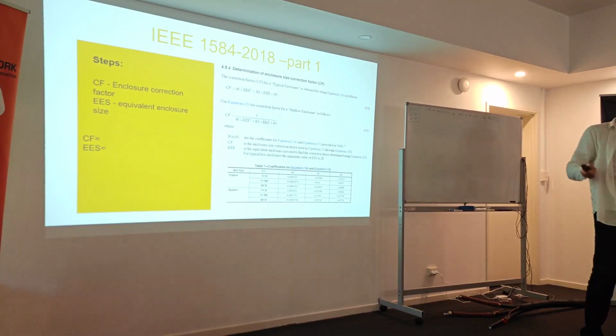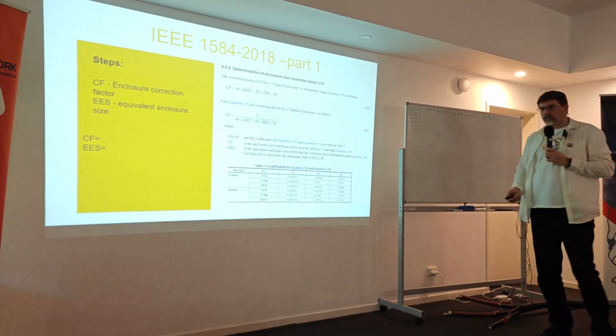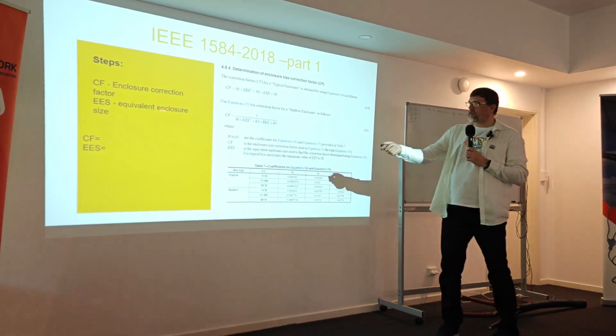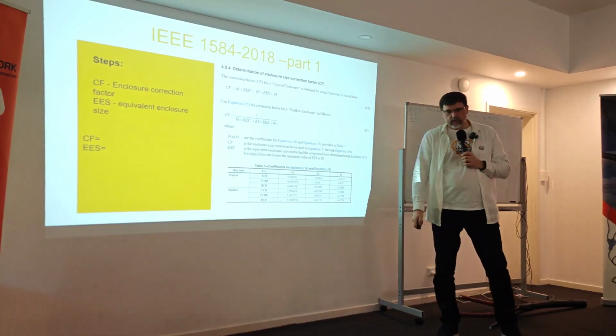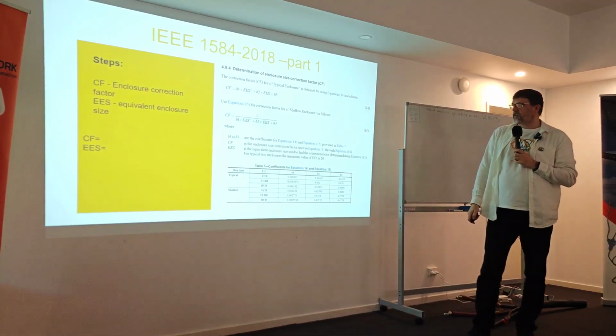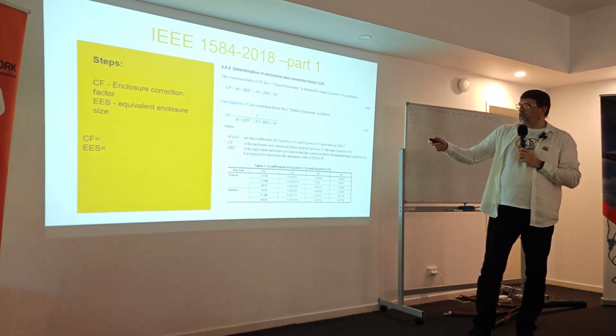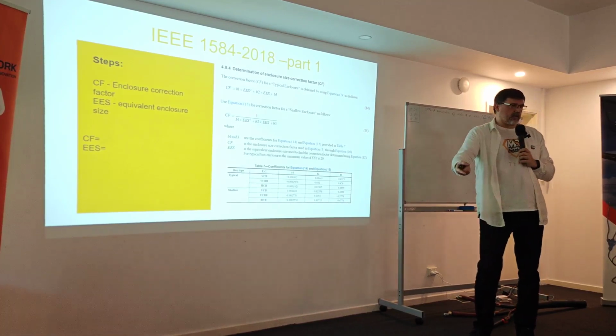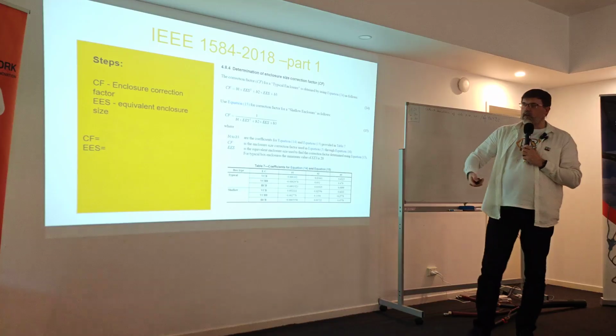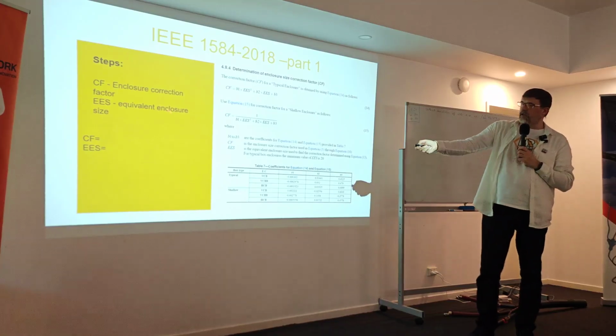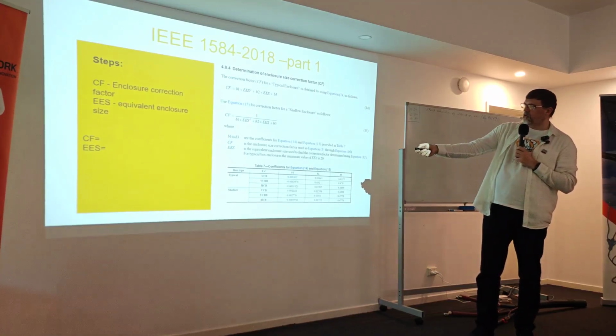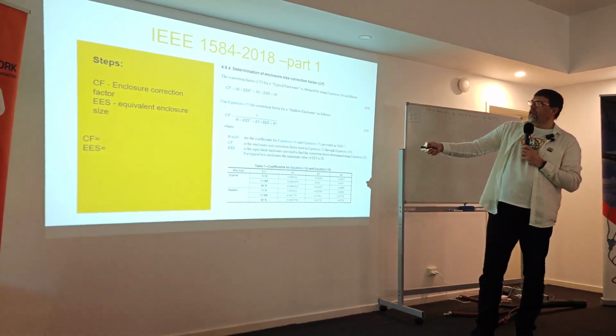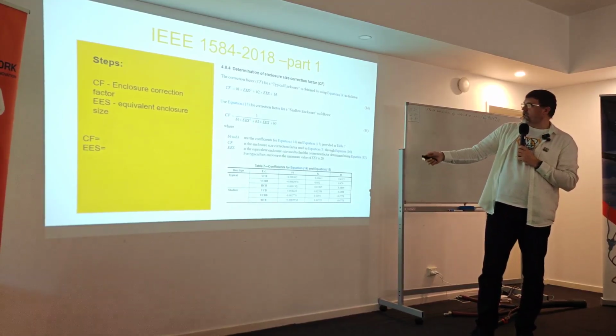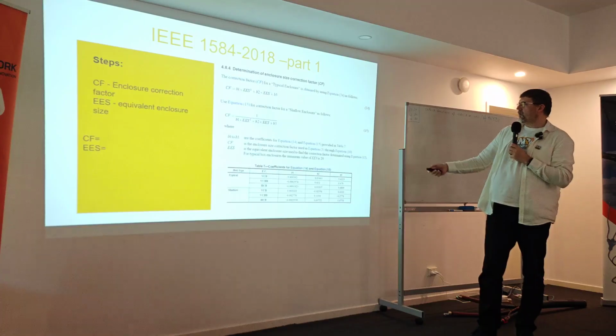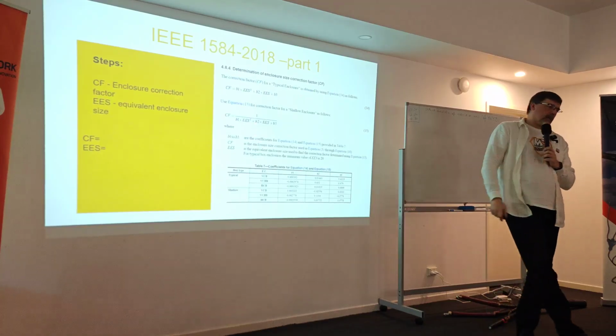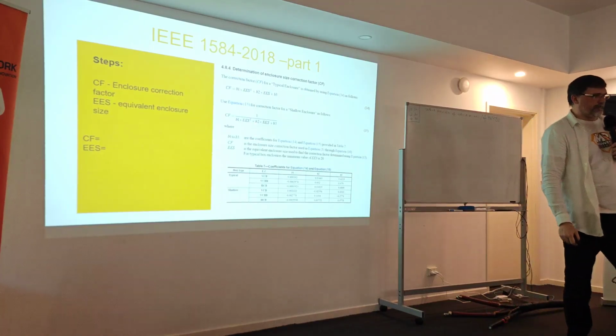Second thing, we go to the point because now we have to calculate the energy. So we need a few things before. We need the correction factor for the enclosure. This is the tricky part because the enclosures have the reference values that they tested. Everything is based on those reference values. So now we have to recalculate something called equivalent enclosure size, to get this point. It's the recalculation factor for the size of the enclosure.